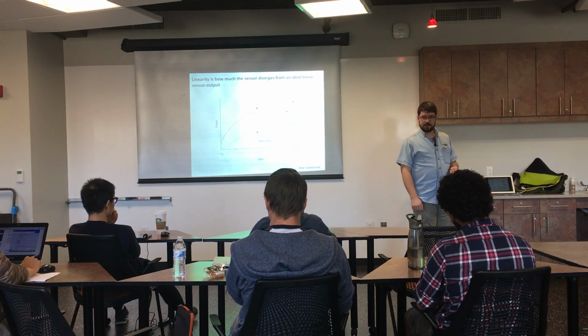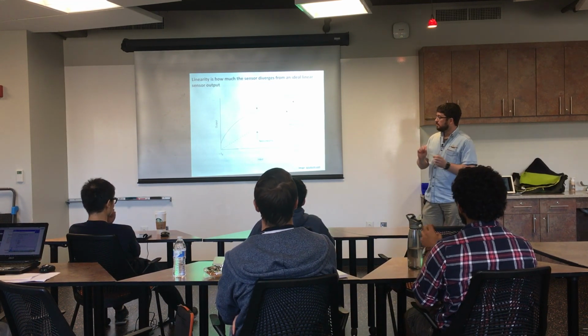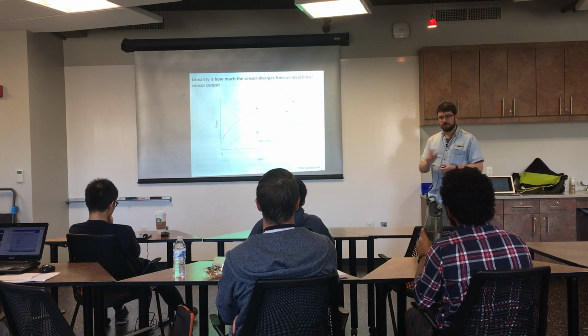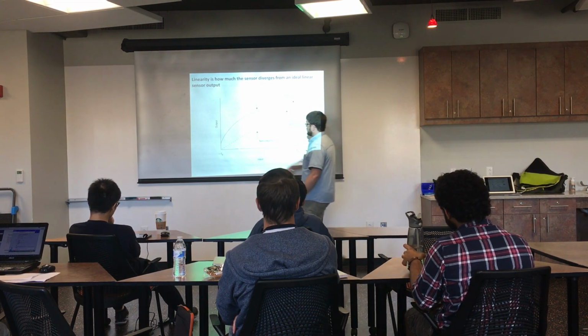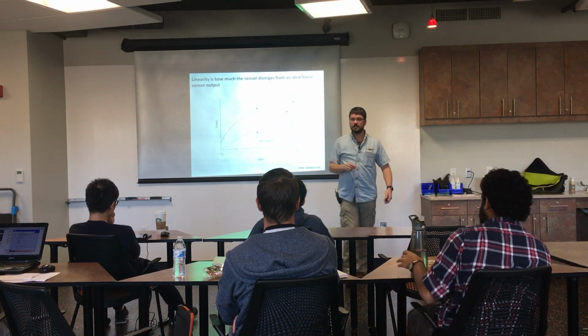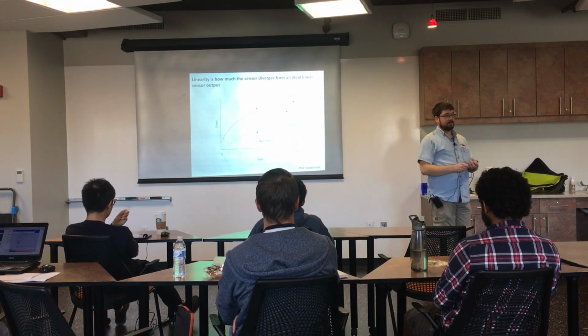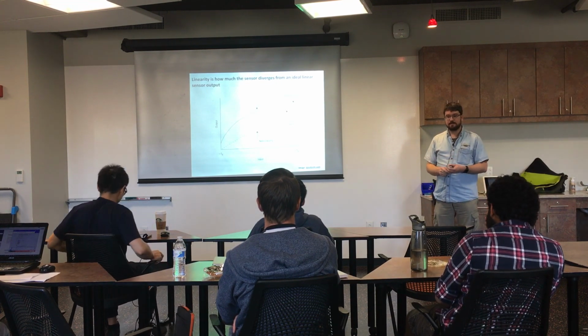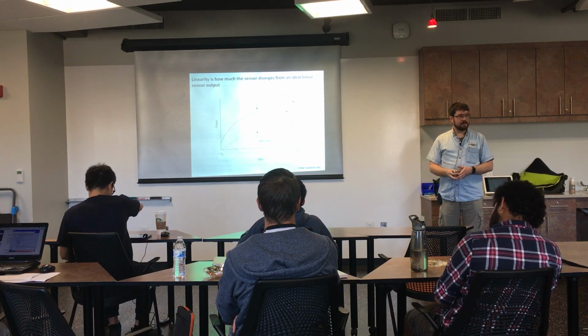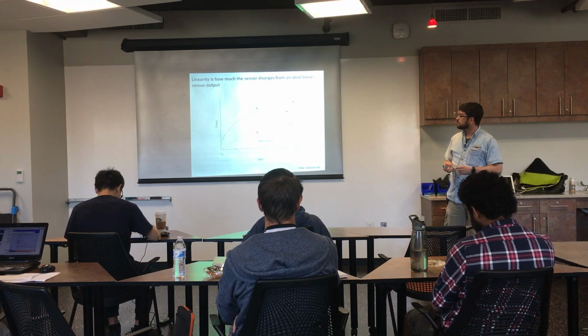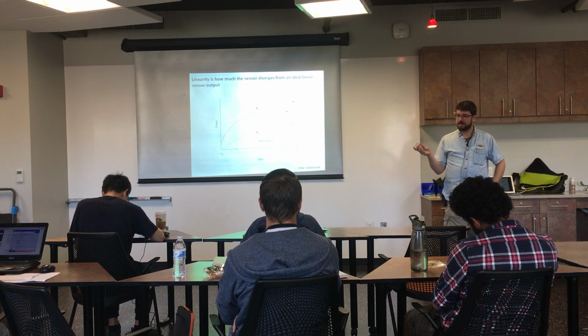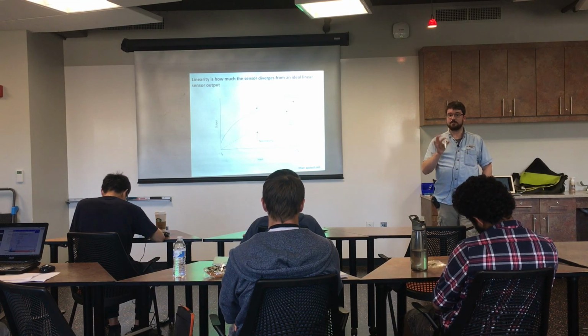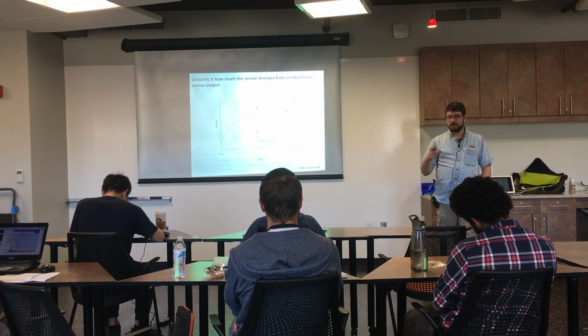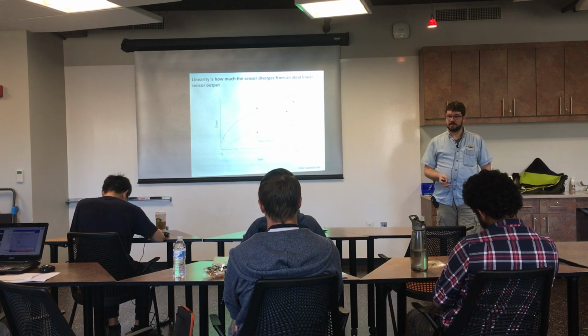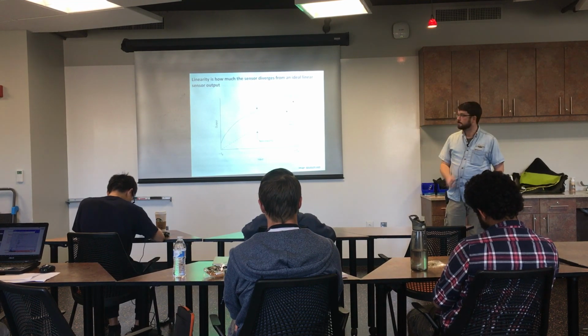Very few transducers are linear, strictly. A lot of times they're very nonlinear at the ends of their range, and the center of the range is the most linear. But this would be a really nasty nonlinear transducer. So in that case, you could either find a different or a better transducer or do a more complicated calibration and data reduction routine. But ideally, you want a nice linear transducer. Most of them are. The linearity is generally specified as a percentage of full scale within a certain range. So for the center 80% of the useful range of the transducer, maybe a 0.5% full scale nonlinearity would be a pretty typical spec for something.